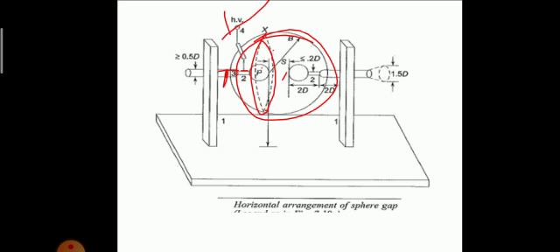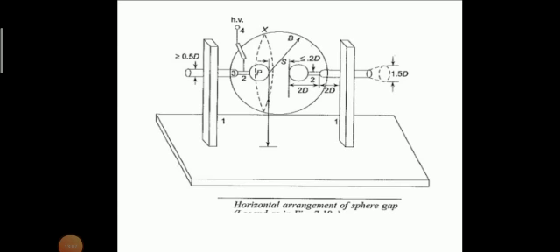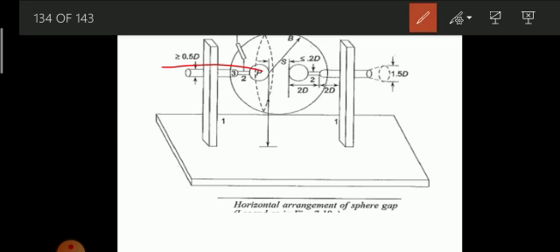Now here, what we do is the voltage to be measured is applied between the two spheres. Here and here, it's applied with a spacing of S between them. So it measures the spark over voltage. Now generally a series resistance is connected between the source and the sphere gap. If this is the source, which I have connected to the voltage source, here I'll have one resistance. The work of this resistance is, first, to limit the breakdown current, and second, to suppress the unwanted oscillations in the source voltage if the breakdown of this gap occurs.